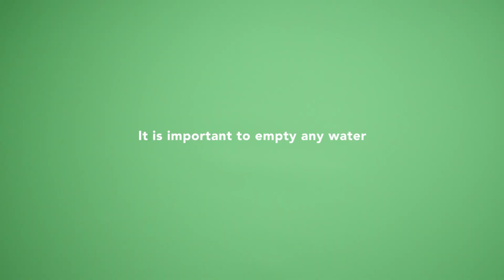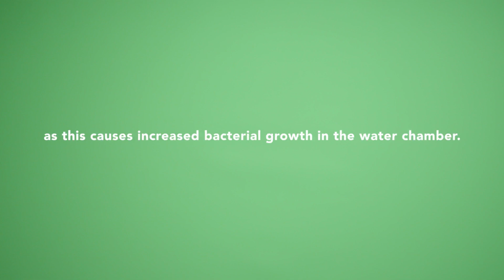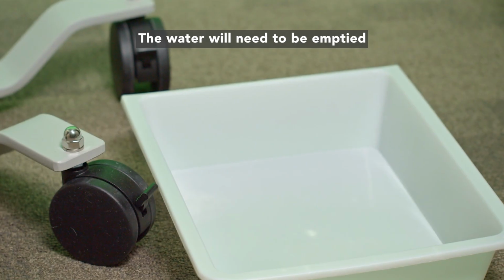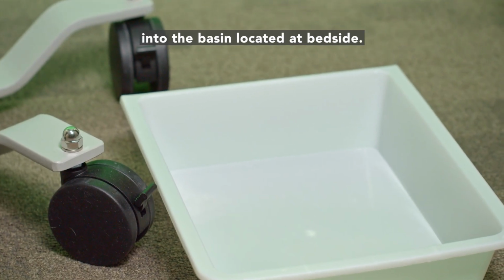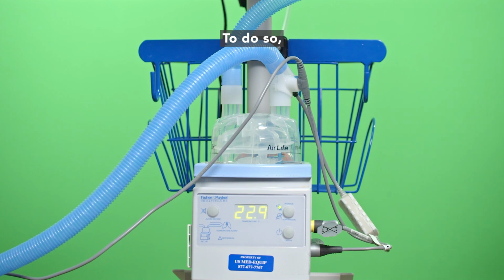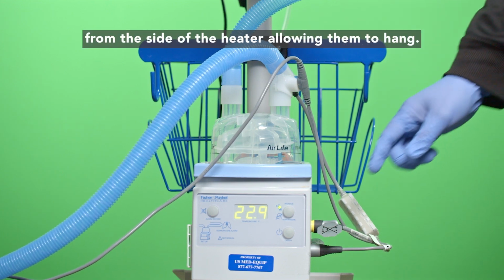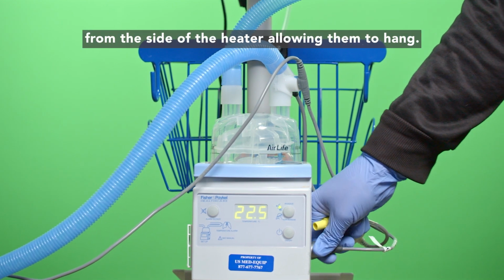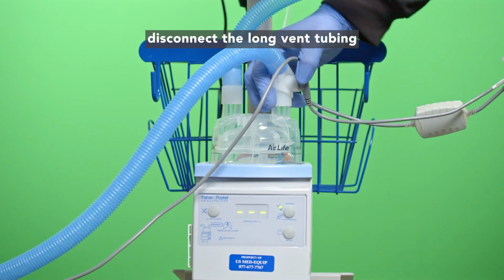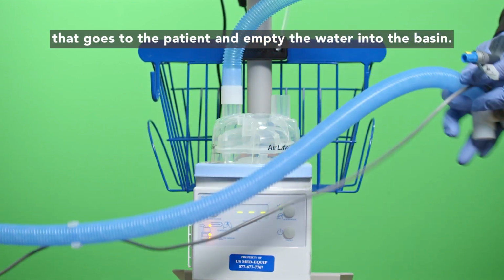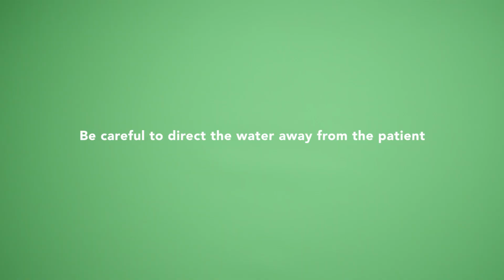It is important to empty any water that accumulates within the ventilator circuit. Do not empty the water back into the heater, as this causes increased bacterial growth in the water chamber. The water will need to be emptied into the basin located at bedside. To do so, disconnect the blue and yellow wires from the side of the heater, allowing them to hang. At the heater, disconnect the long vent tubing that goes to the patient and empty the water into the basin. Be careful to direct water away from the patient and to keep the blue and yellow wires dry.